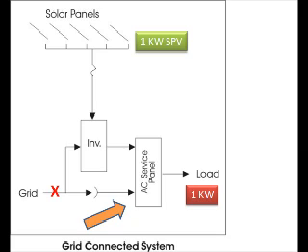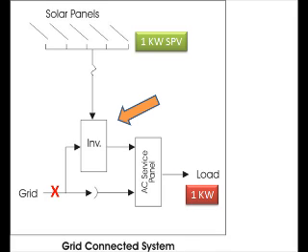To overcome these problems, on-grid systems are designed. These systems do not use batteries. In any on-grid setup, you get grid power connected to your distribution panel where various loads are connected. We install a solar inverter with the panel. This inverter gets a sample of grid power and produces power of exact electrical parameters of the grid. The power so generated is directly injected into your local distribution panel. If the load is 1 kilowatt and generation is also 1 kilowatt, the entire power is drawn from solar.